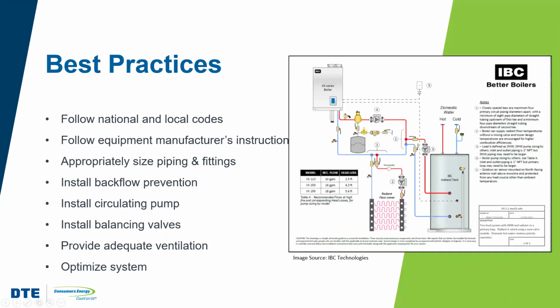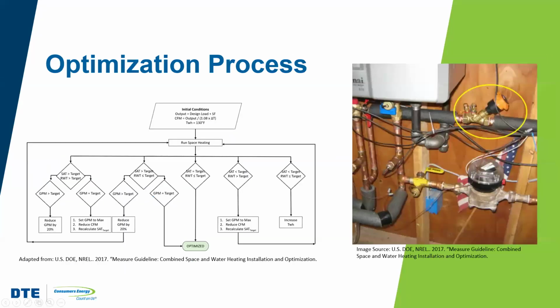So yeah, when you have a combination system, you want to make sure that you're following the local codes, national and local codes. You want to make sure also that you follow the manufacturer's instructions for how to install that piping distribution system. You want to appropriately size the pipe and the fittings. You definitely want to include backflow prevention, and make sure you've got those balancing valves in that system. Oftentimes, when you have a combination system, you may have to go through an optimization process, right?